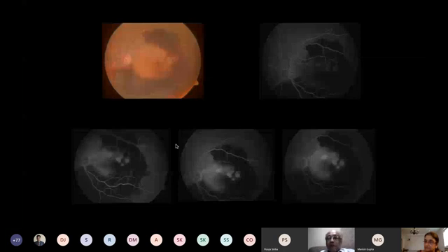Okay. So is that a vitreous floater you're dealing with? Vitreous floaters are a possibility. I would think more what you mentioned, an artifact on the fundus camera itself is causing that for him once in a while. But an artifact would usually remain fixed at one point. Whenever you're taking the images, your artifact will be at the same place in all your images. It's not going to really move around so much. But if while you are trying to focus you see a black spot floating around, then probably there's something in the vitreous which you have to get out of your field of view. Yeah, I agree with you.